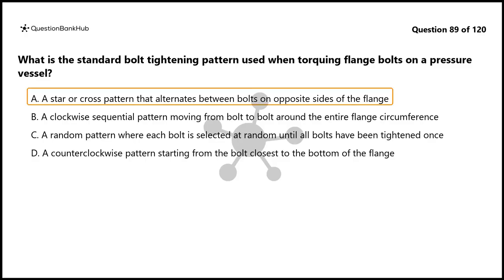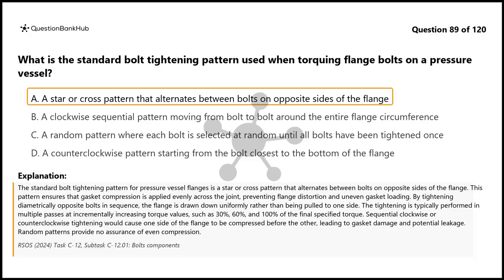The correct answer is A. The standard bolt tightening pattern for pressure vessel flanges is a star or cross pattern that alternates between bolts on opposite sides of the flange. This pattern ensures that gasket compression is applied evenly across the joint, preventing flange distortion and uneven gasket loading. By tightening diametrically opposite bolts in sequence, the flange is drawn down uniformly rather than being pulled to one side.